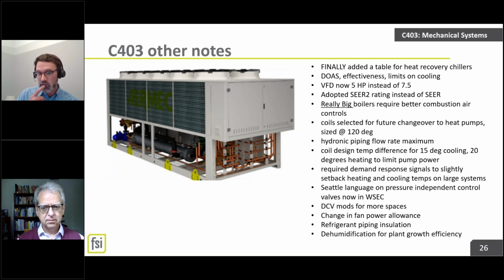Something Duane said, I want to make sure it's super clear. All the mechanical engineers in the room might be raising their hands about this one. When you replace with a different temperature system, you have to replace the thing making the heat, the boiler, the heat recovery chiller, whatever. The coil on the other end needs to be resized because it needs more fins for that lower temperature. It needs more area. But the piping in the middle, as long as you didn't change the temperature delta between the supply and return, the piping gets to stay, as long as it's okay. Investigate your piping; it might be falling apart.